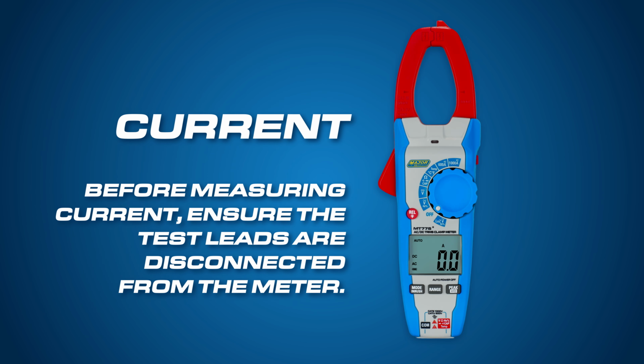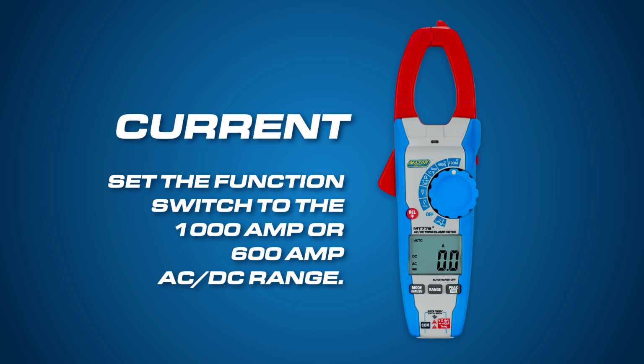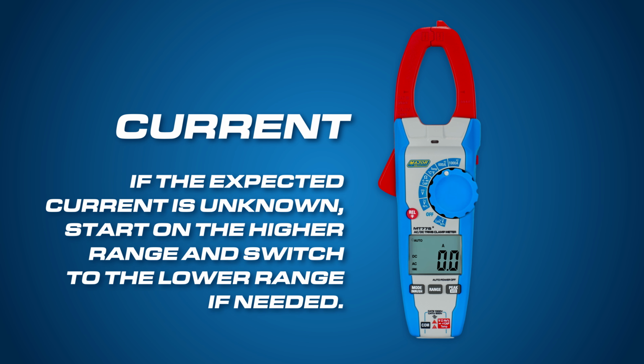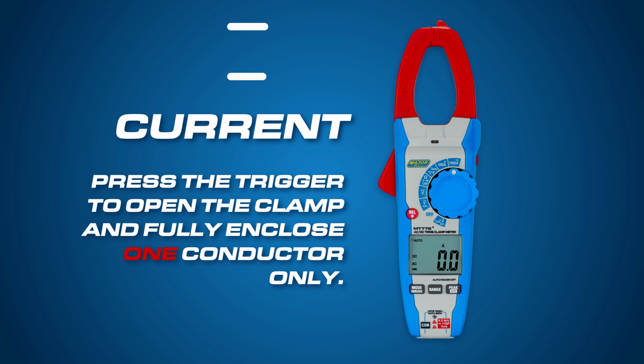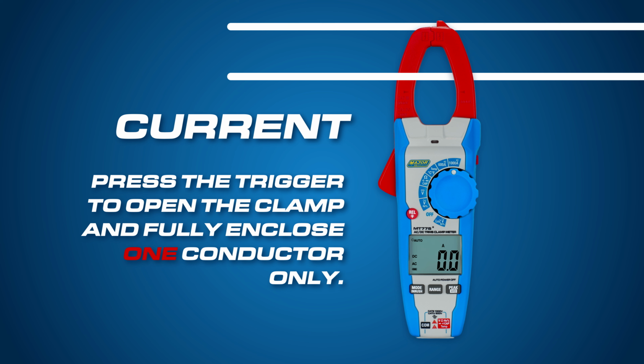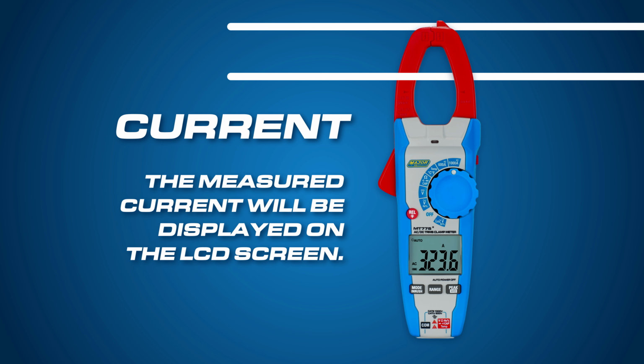Current measurement. Before measuring current, ensure the test leads are disconnected from the meter. Set the function switch to the 1000 amp or 600 amp AC/DC range. If the expected current is unknown, start on the higher range and switch to the lower range if needed. Press the trigger to open the clamp and fully enclose one conductor only. The measured current will be displayed on the LCD screen.